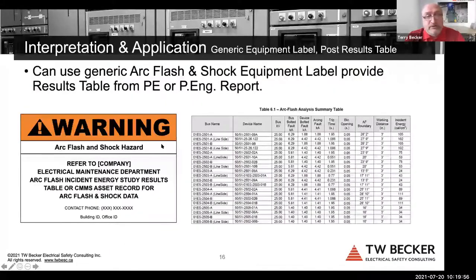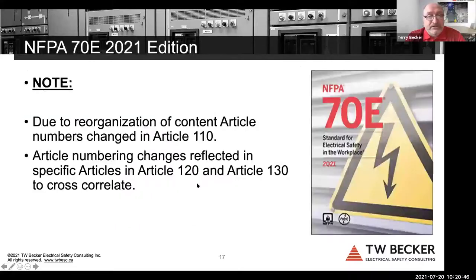The other option, other than labels, and I'm starting to encourage this with large clients that have the right staff to manage this, is to go with a generic label and point to the results table, right? So you could replace all of your arc flash and shock labels one more time, huge cost again, but only one more time with this generic label. Then take the results tables from the engineer's report, put them into a spreadsheet or a table, and issue that table in a PDF to your staff electricians and your contractors proactively. Post it, laminate it in electrical rooms, so hard copy PDFs. And really, to me, this is for large industrial, commercial, institutional sites with appropriate staff to manage this. This is how we should give the information to the workers that are exposed. So again, FYI, this is now allowed. It was allowed in the last edition of 70E and Z462.